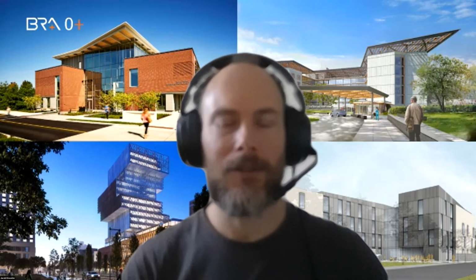The controls are the one piece that we're particularly sensitive to - setting that up properly from the beginning, commissioning it properly from the beginning, and having intuitive, adjustable controls for the key variables so that over time you can make sure the system is staying balanced as intended. So you may want to have a third party do a review every couple of years just to make sure things are on track. But it's such a slow process - the temperature fluctuations in that amount of mass in the ground is such a slow process that you can schedule that at your convenience, and it's a pretty minor effort.